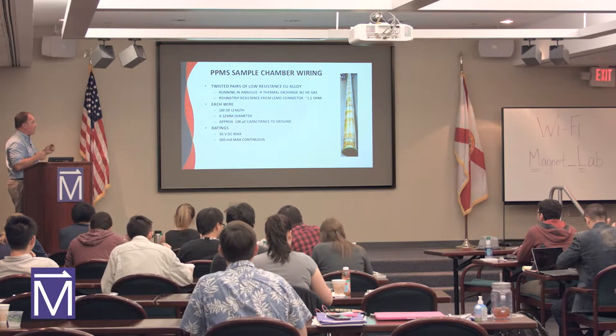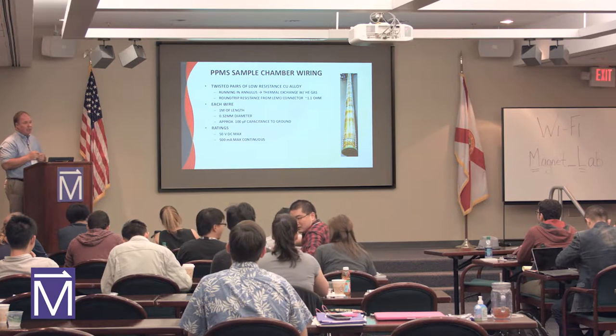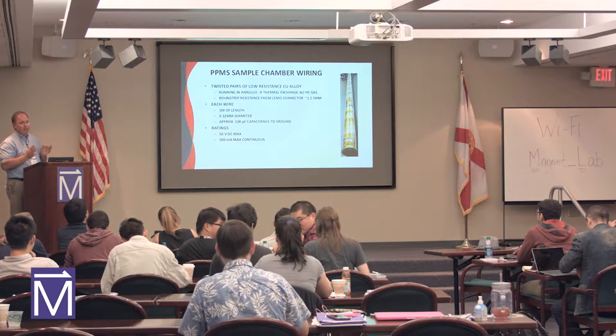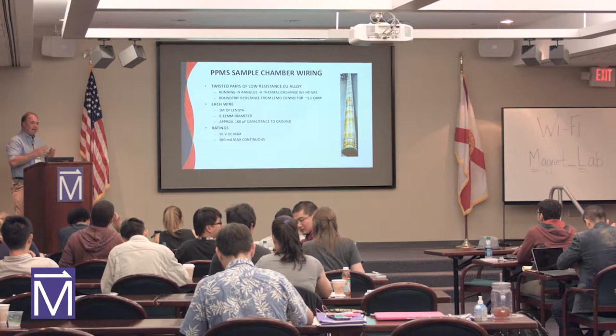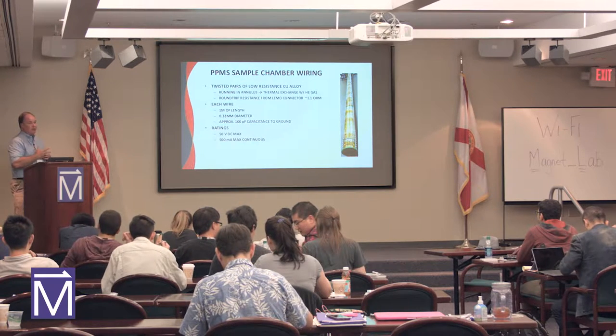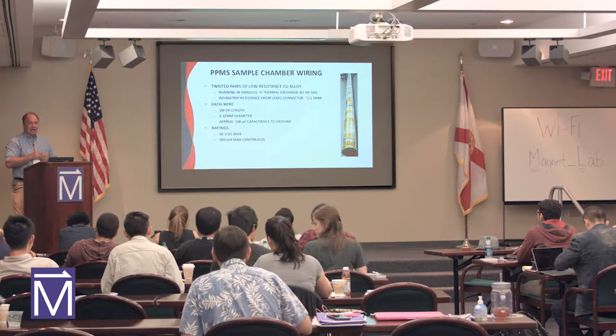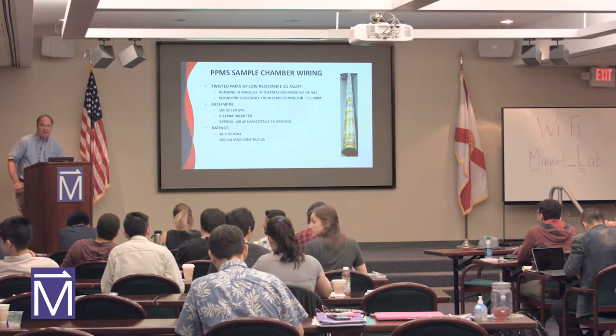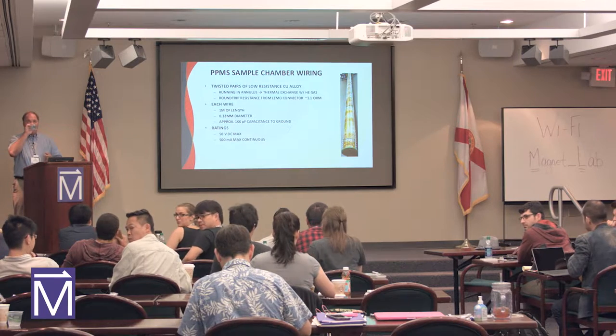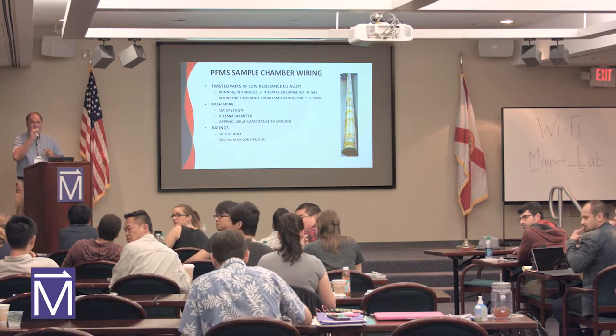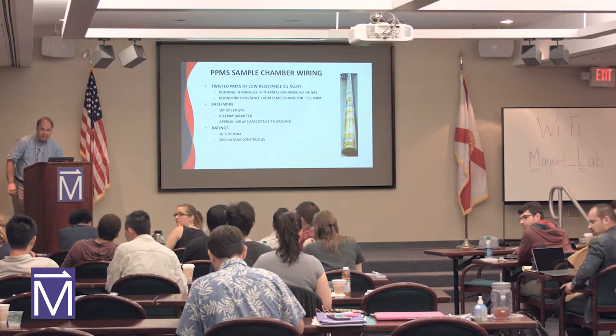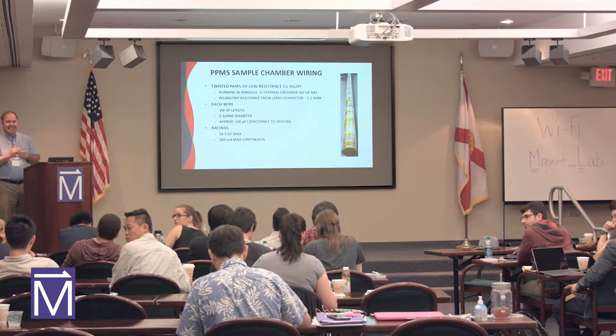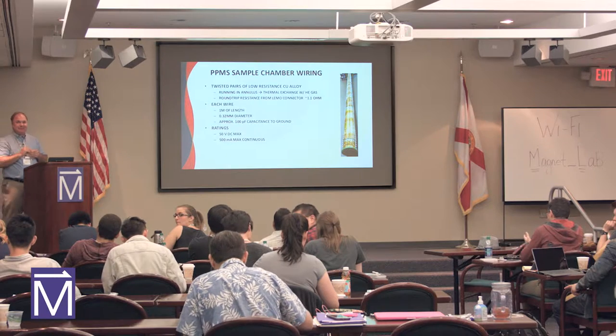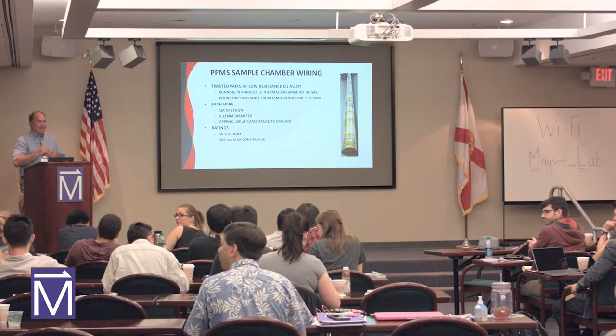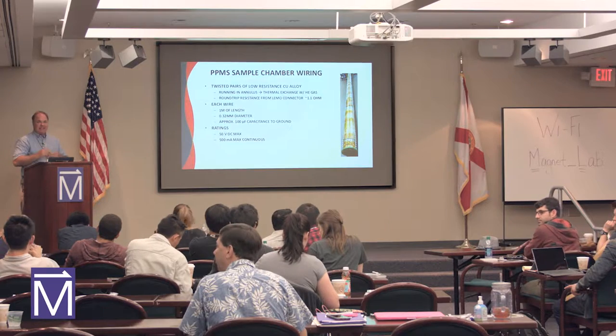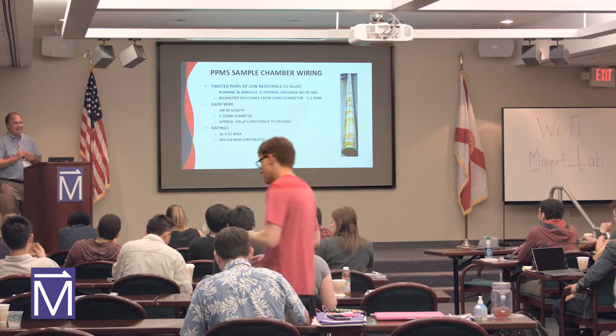The one thing to make note of is the breakdown voltage of these wires. You can only put 50 volts on these wires. Some people ask, can I put higher voltage on them? And you're limited to 50 volts in this application. Some people don't ask, and on our probes out there, they'll put hundreds of volts and actually ruin the twisted pairs, and you won't realize it until the next user shows up. And suddenly, hey, how come I get this resistance between pairs? So again, when somebody tells you the voltage limit, please listen and please obey, because it won't just affect you.